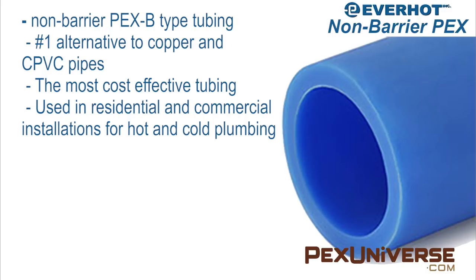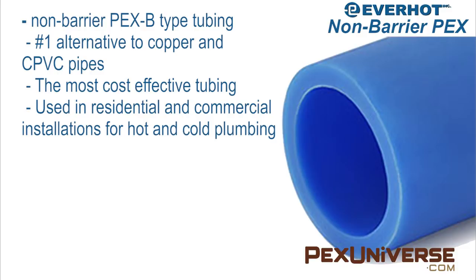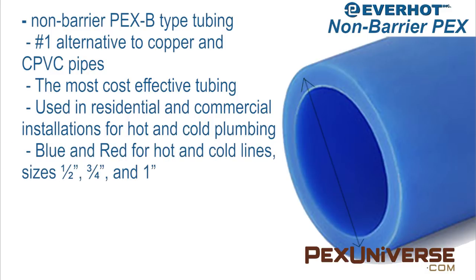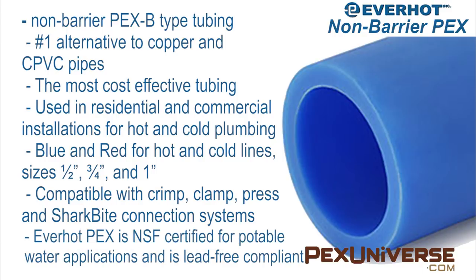It can be used in open-type heating systems where all the components including valves, pumps, fittings, etc. are non-corrosive, meaning brass, bronze, and stainless steel. It can come in sizes of a half inch, three-quarter inch, and one inch. It's compatible with crimp, clamp, press, and SharkBite connection systems. EverHot PEX is NSF certified for potable water applications including hot chlorinated water and is lead-free compliant.